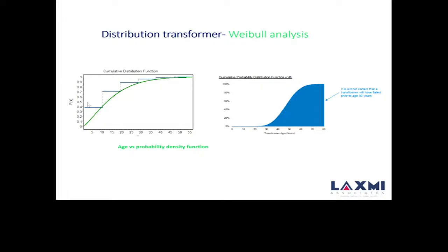Based on this, because the fleet size is very big at 12,000, we did Weibull analysis to derive the mean life of the transformer in the system. By doing failure analysis based on Weibull analysis, we find that the mean life of the distribution transformer in their system falls around 16 to 17 years.